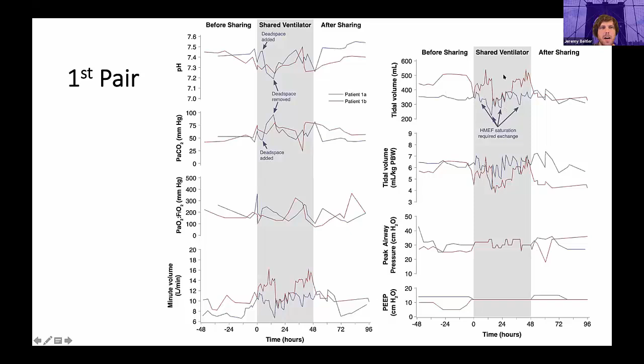The reason that happened was because we were using pressure control as required by our protocol, and the HME filter was getting saturated quite rapidly. The reason was that the first pair was the one pair that we did on an anesthesia machine. We didn't fully anticipate how quickly the CO2 absorbent in the anesthesia machine would get exhausted. It was being changed maybe 3 or 4 times a day.